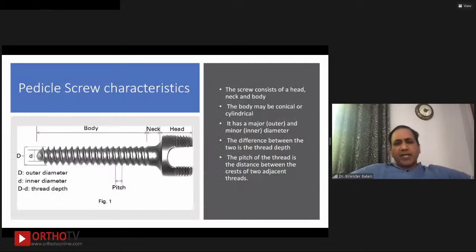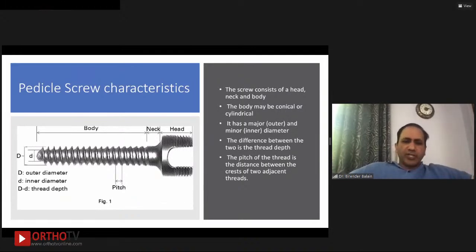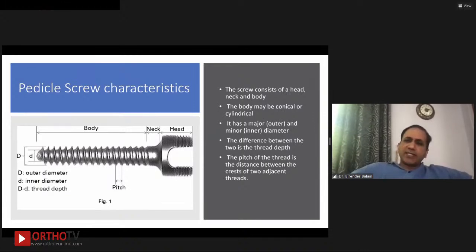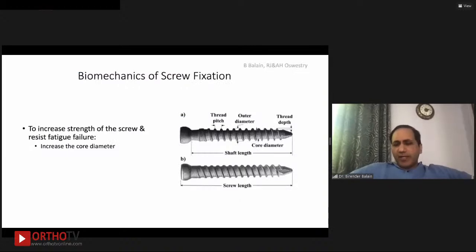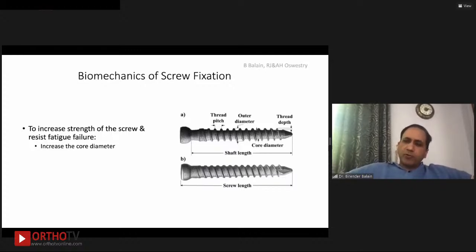Looking at pedicle screw characteristics — the head, neck, body, outer diameter, thread depth — two important features are the pitch (the distance between two threads) and the difference between outer and inner diameter. To increase screw strength and resist fatigue failure, you need to increase the core diameter — the inner diameter. The bigger the core diameter, the stronger and more fatigue-resistant the screw will be. For cannulated screws, the width of the thread (the difference between the outer thread diameter and the outer diameter of the inner core) determines purchase in bone, while screw strength is minimally affected by the hollowness.